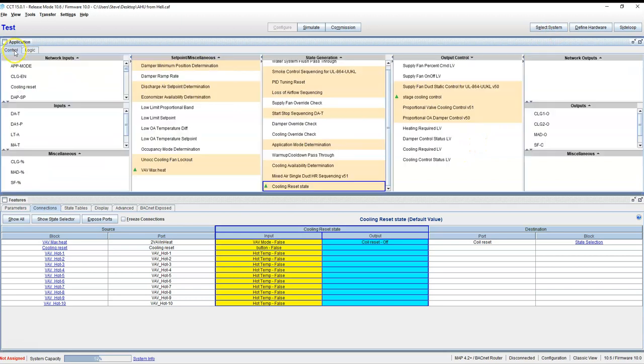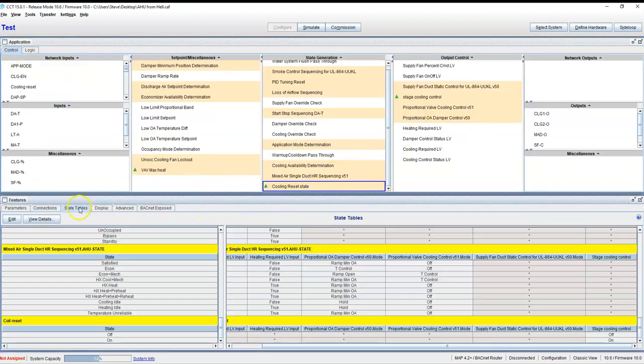If the mode's off and button's on, we stay in regular mode. And that's going out to a cooling reset. That cooling reset is going to a state table down here which turns on stage cooling control.